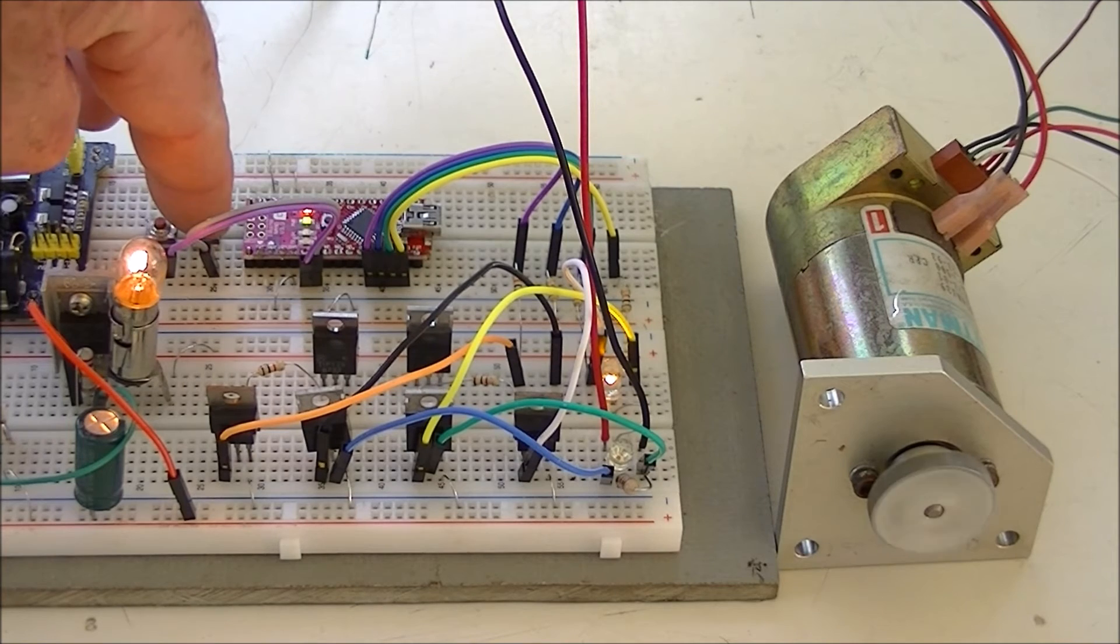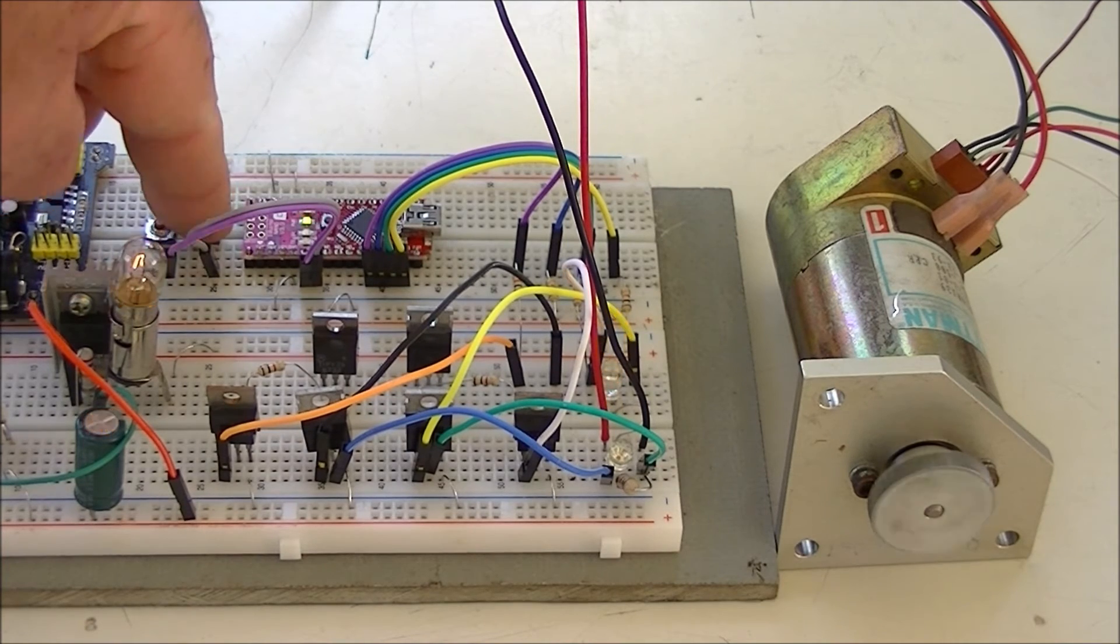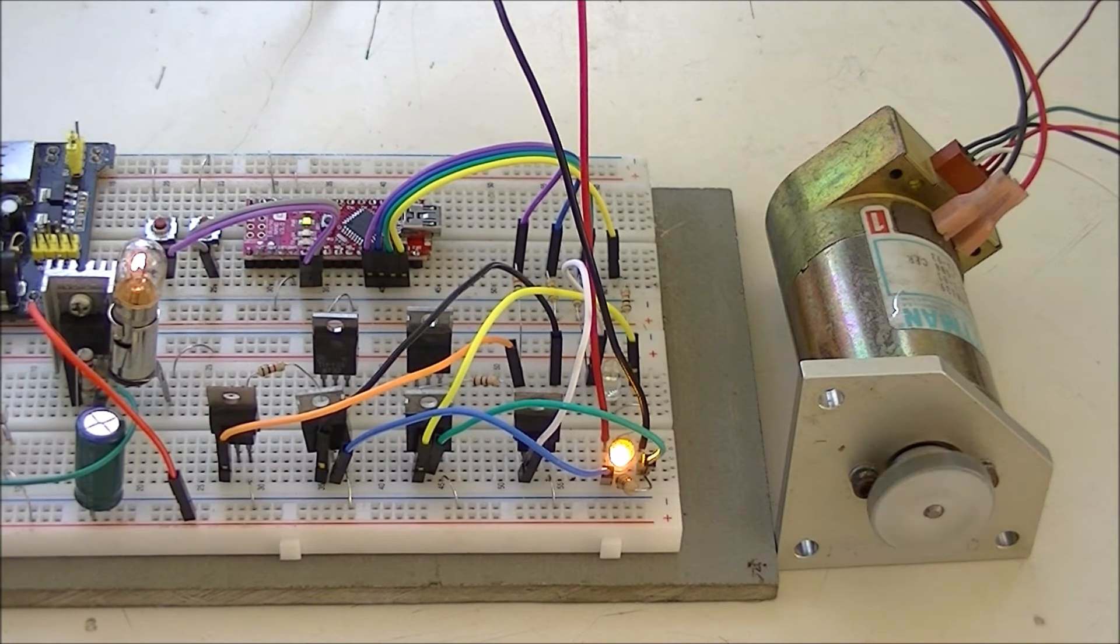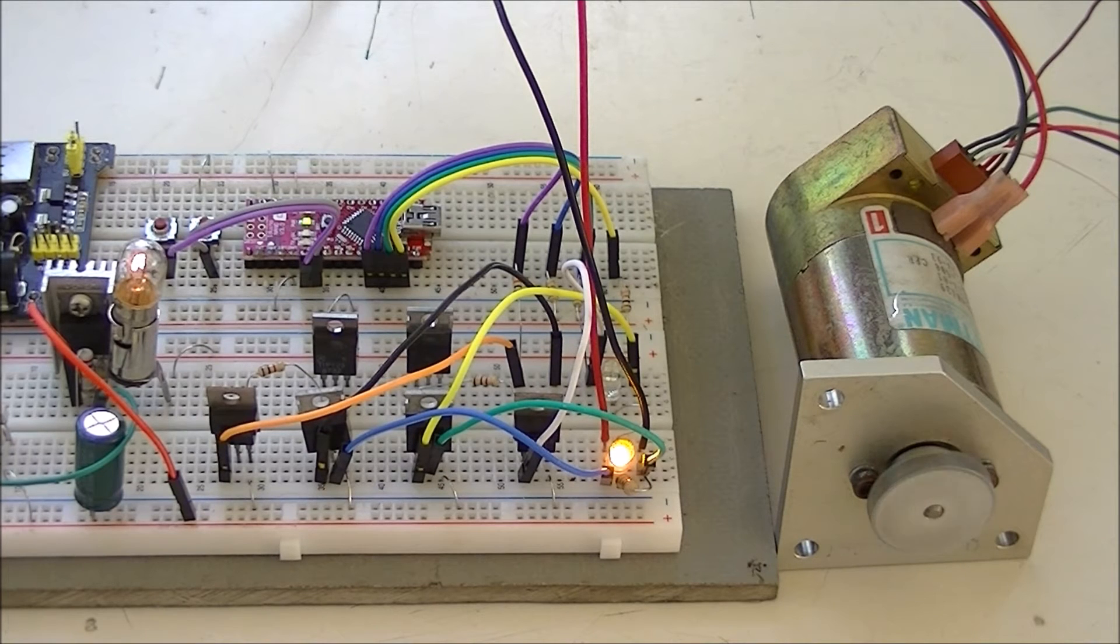Again. Counterclockwise, when I press the switch, stops and reverses. This is a point that a lot of people aren't getting. When you're starting, when you reverse polarity on these motors, let it stop first. Give it a chance. And that's in the programming.